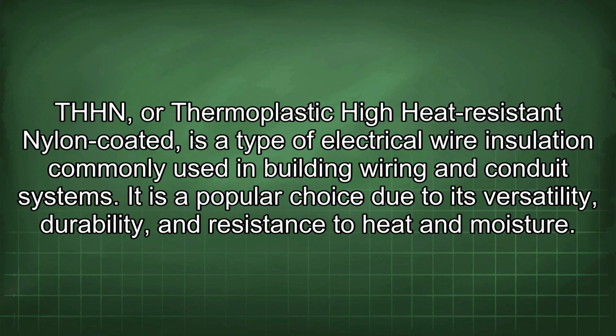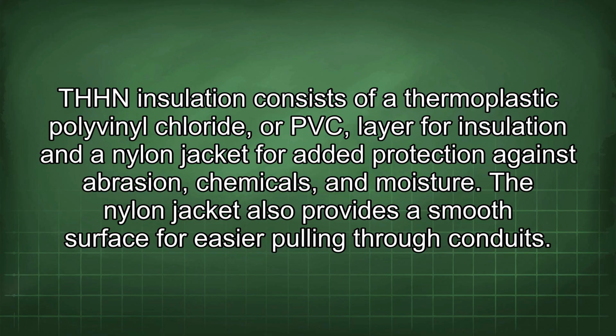THHN, or thermoplastic high heat resistant nylon coated, is a type of electrical wire insulation commonly used in building wiring and conduit systems. It is a popular choice due to its versatility, durability, and resistance to heat and moisture. THHN insulation consists of a thermoplastic polyvinyl chloride, or PVC, layer for insulation with a nylon jacket for added protection against abrasion, chemicals, and moisture. The nylon jacket also provides a smooth surface for easier pulling through conduits.